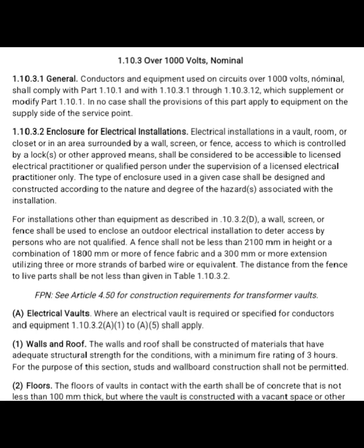A. Electrical vaults. Where an electrical vault is required or specified for conductors and equipment, 1.10.3.2(A)(1) to (A)(5) shall apply. 1. Walls and roofs. The walls and roofs shall be constructed of materials that have adequate structural strength for the conditions, with a minimum fire rating of 3 hours. For the purpose of this section, studs and wallboard construction shall not be permitted. 2. Floors. The floors of vaults in contact with the earth shall be of concrete not less than 100 mm thick, but where the vault is constructed with a vacant space or other stories below it, the floor shall have adequate structural strength for the load imposed on it and a minimum fire resistance of 3 hours.